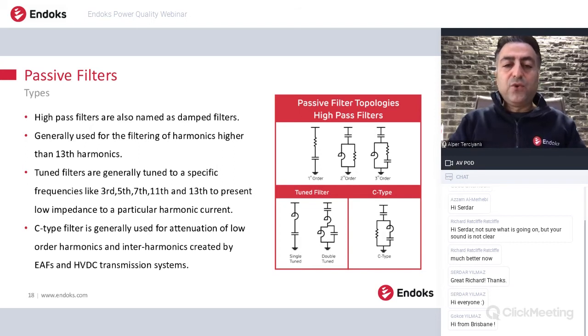You see below the tuned filters. Tuned filters are the common ones. We mostly use these filters. There are some types, like single tuned filters. For example, if we have a load and it creates fifth harmonics, we use a filter having a series resonance frequency of 250 hertz. I mean the inductor and the capacitor form a filter circuit, and the frequency of this filter circuit is 250 hertz.